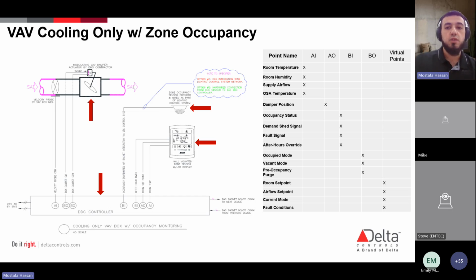So each VAV unit will be directly controlled by its own dedicated EMS controller. There's your DDC or building management EMS controller. That's where everything comes back. The field devices are wired to it. And in this scenario, this is probably not a building level controller, right? This doesn't need a lot of supervisory horsepower or a ton of inputs and outputs. In this case, it's probably an application specific controller, just because you have additional things like your occupancy sensor. This is more than your typical points for a VAV. So maybe an application specific controller will suffice.